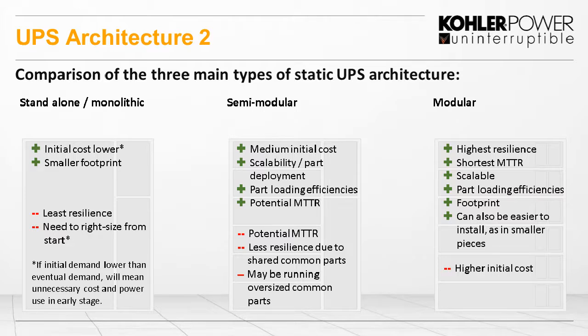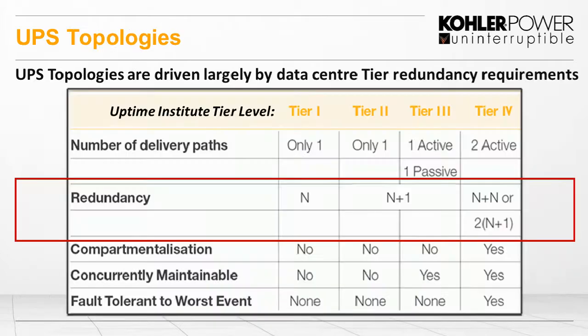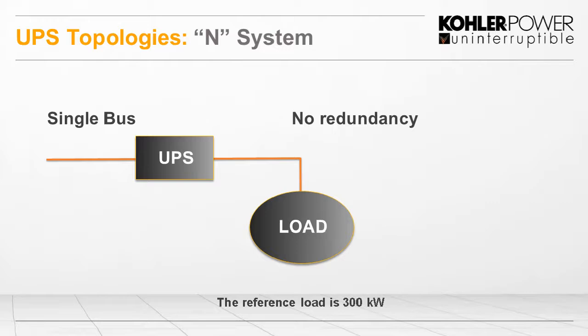So, one of the things we looked at is the redundancy and resilience of these systems. So we look at the different UPS topologies that we see. So in the Uptime Institute, we have the different tier levels, tier 1 to tier 4. And you look at the chart in front of you, and we're looking at the redundancy part. So tier 1 is N, tier 2 and 3 are N plus 1, tier 4, N plus N, or 2N plus 1. So I'm going to run through what those redundancy levels mean. So first of all, we look at the N system. Now, an N system, in this case, we're looking at a reference load of 300 kilowatts. So we have a single UPS feeding a single load of 300 kilowatts. As you see, there's no redundancy there. If that UPS isn't working, nothing will be.